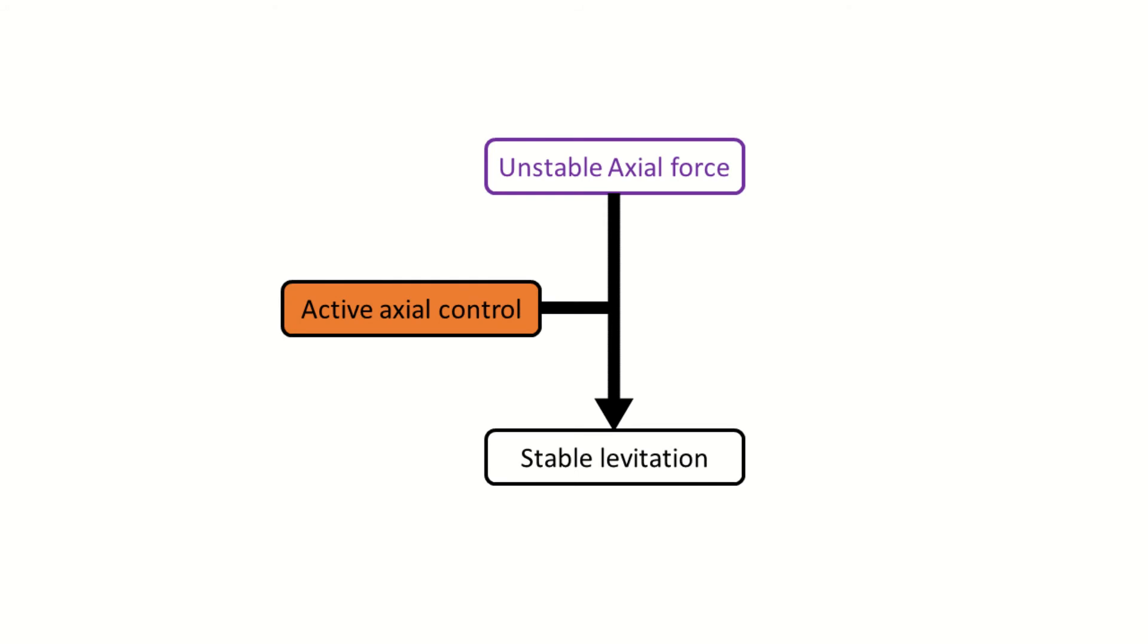By regulating the stator current, it is possible to generate a suspension force that pushes the rotor back to the center, compensating the unstable force by the permanent magnet radial bearings. The same currents can be used to generate motor torque.